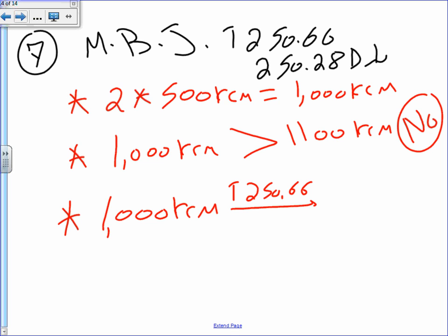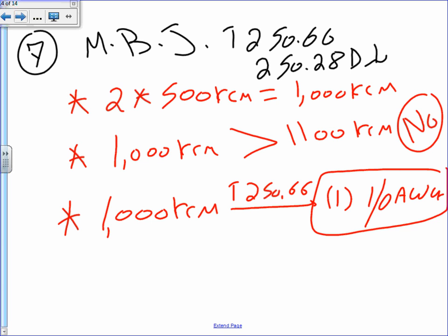And that'll get you, what did we come up with again? One conductor, 1/0 AWG THHW. No, it goes to 2/0, sorry. To what? 1,000, it's 2/0. I was reading the wrong number. It's all right. Next time we'll charge you for that. Okay. To what?